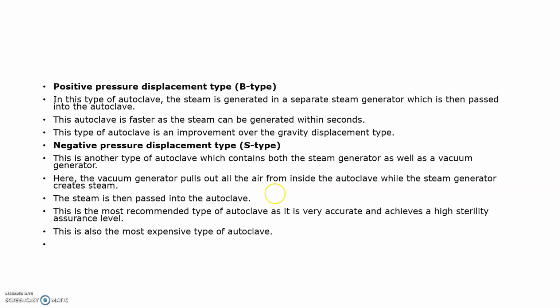Next is the positive pressure displacement type, that is B type. In this type of autoclave, steam is generated in a separate steam generator and that steam is then passed into the autoclave. This autoclave is faster as the steam can be generated within seconds. And this type is an improvement over the gravity displacement type. Next we are discussing S-type or negative pressure displacement type autoclave.